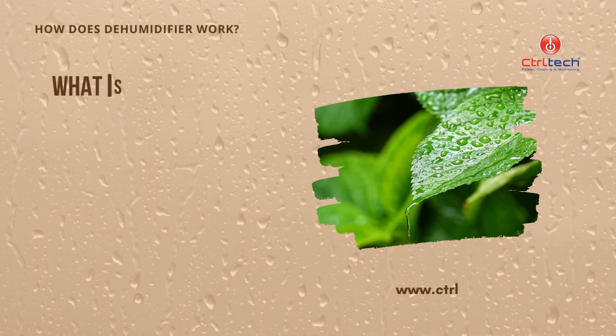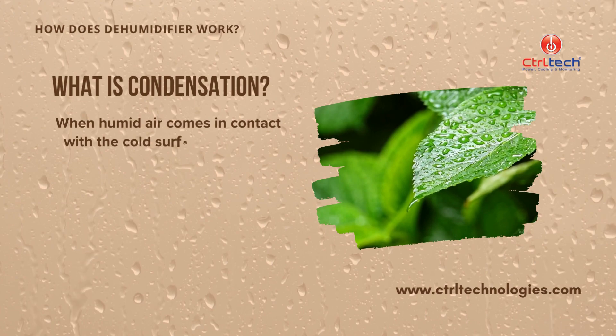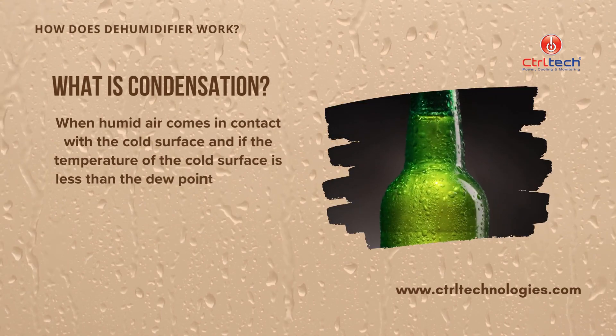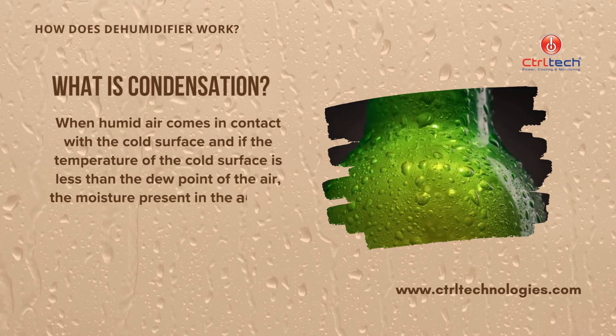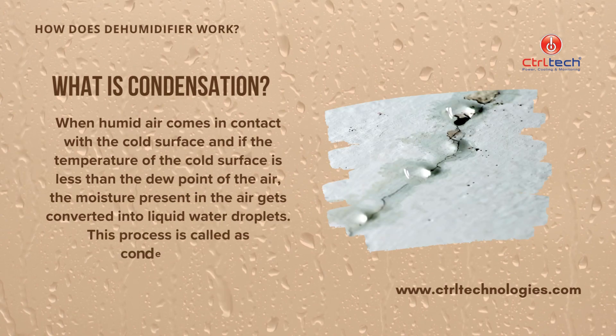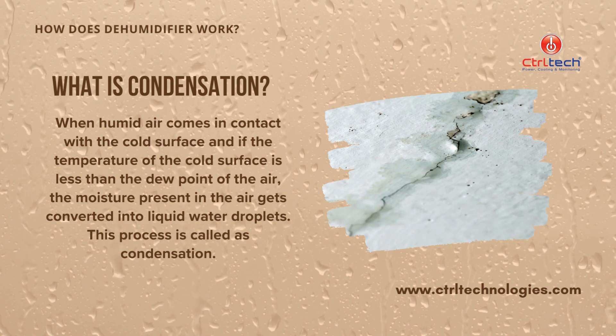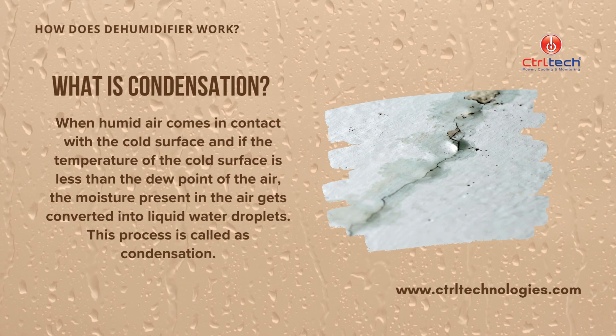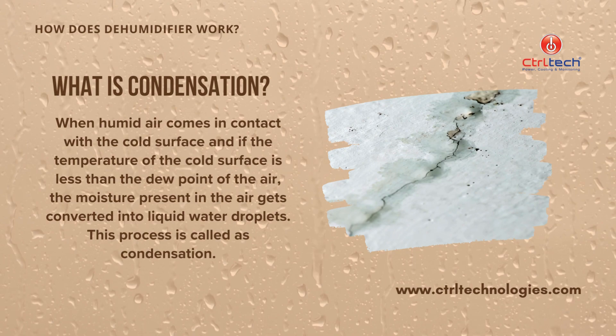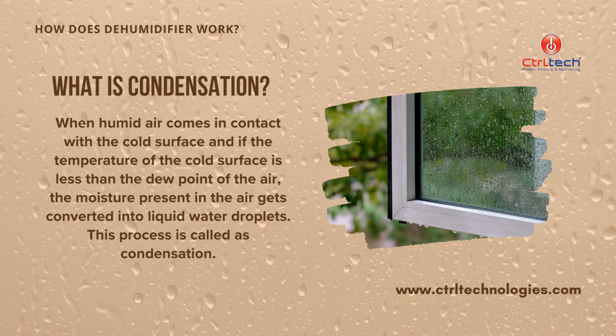To understand the condensation dehumidifier working principle, let's first understand what condensation is. When humid air comes in contact with a cold surface and the temperature of that cold surface is less than the dew point of the air, then the moisture present in the air gets converted into liquid water droplets. For example, in summer when there is a hot and humid climate outside and you run the air conditioner at night inside your home, in the morning you find water drops on the window glass — that is because of condensation of moisture available in the air. This is condensation.